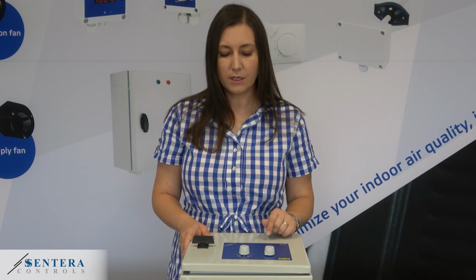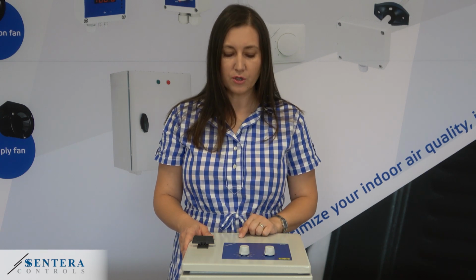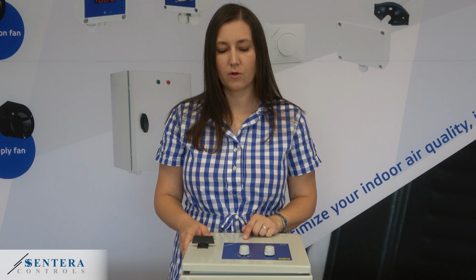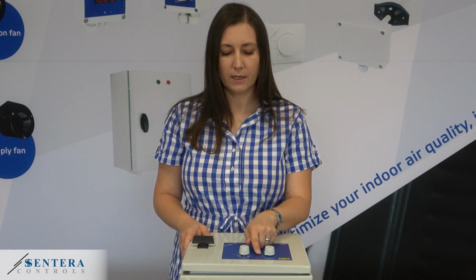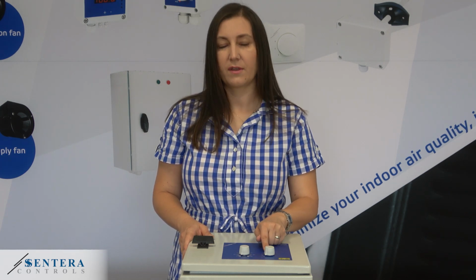These connections are just enough to get your motor running based on the temperature measured by the PT500 temperature probe that's installed in the correct place. Like this, the controller will run based on the settings done using the two knobs on the enclosure. This one is for temperature set point and this is the control knob. Automatic mode, off, and then the 5 output steps.